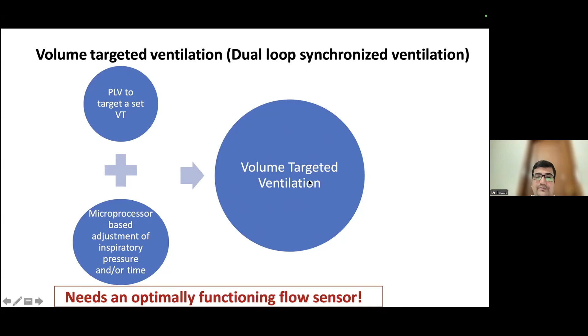This is the basic principle behind volume targeted ventilation. The mechanical ventilator gives a test inflation with a particular PIP, and then it measures the tidal volume provided to the baby. By measuring the tidal volume delivered to the baby, it compares it with the target tidal volume of the previous breath. If the delivered tidal volume is less than the target tidal volume, it will increase the inflation pressure in the subsequent breaths, so that the next breaths are given with a higher inflation pressure and hence higher tidal volume, so that the delivered tidal volume matches the set tidal volume.